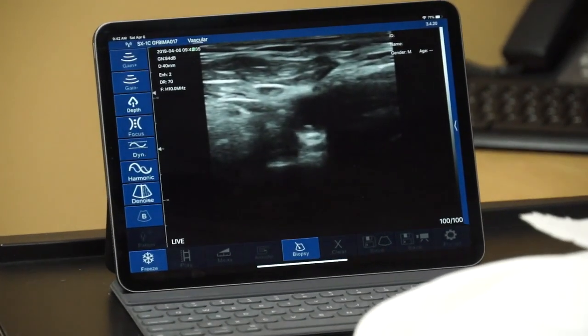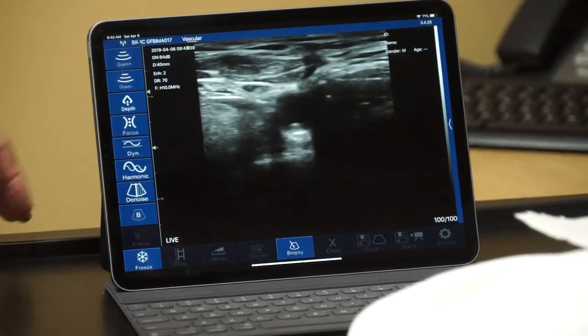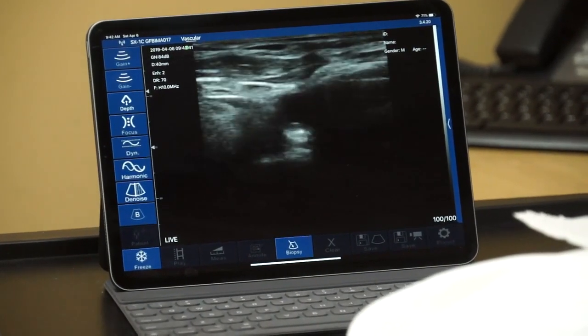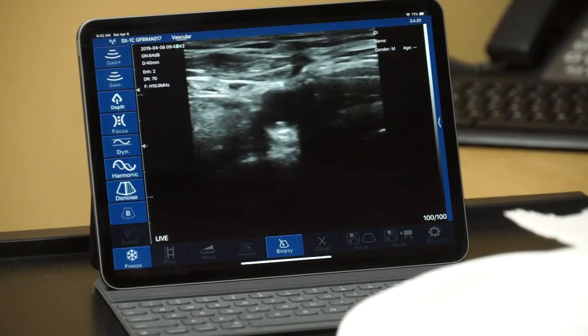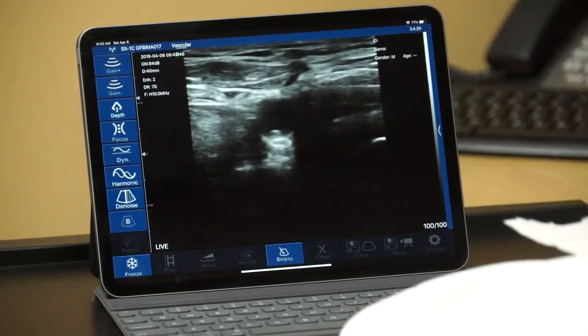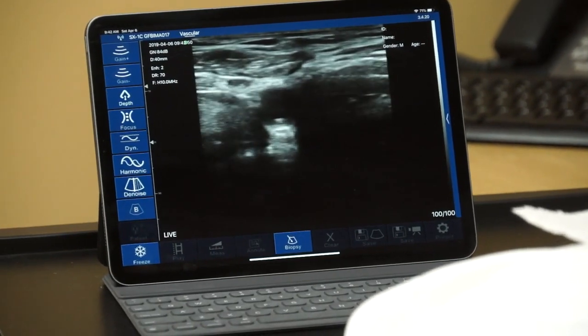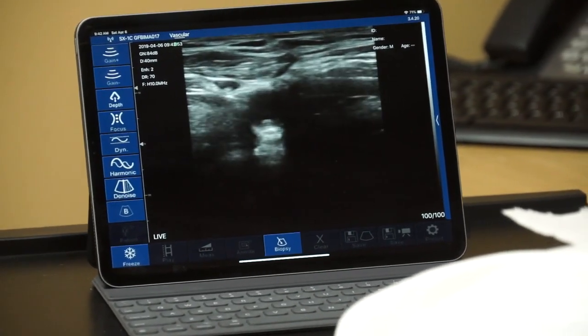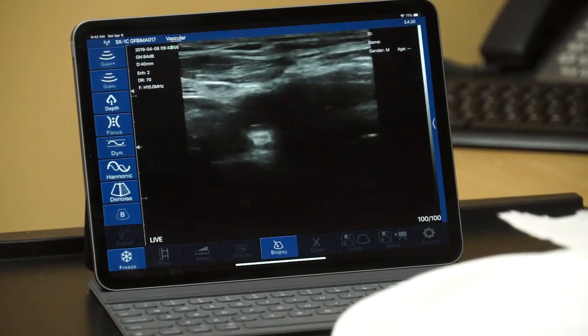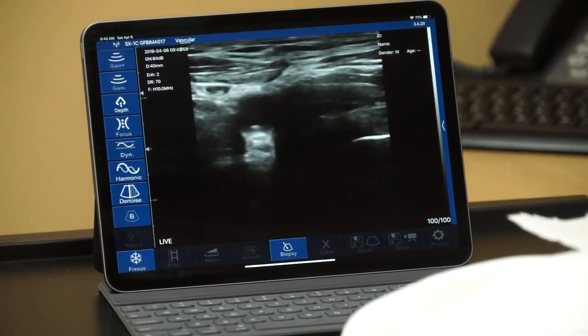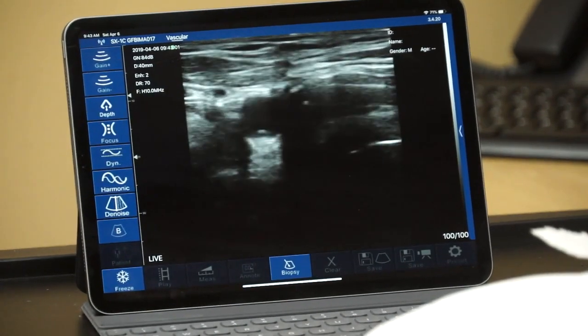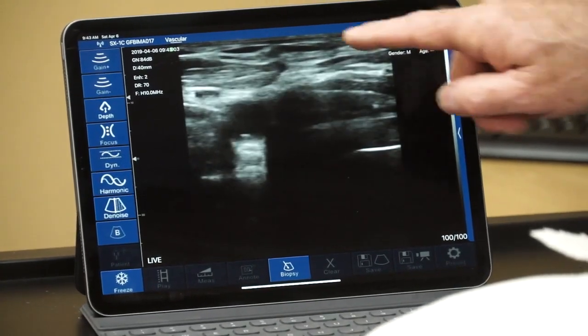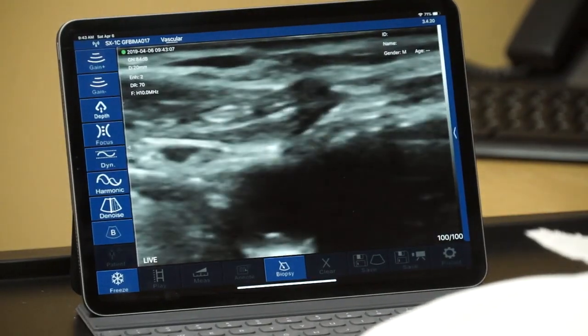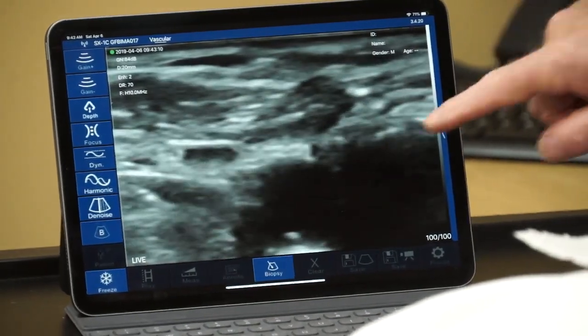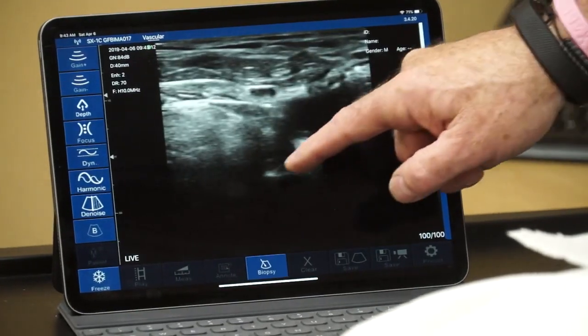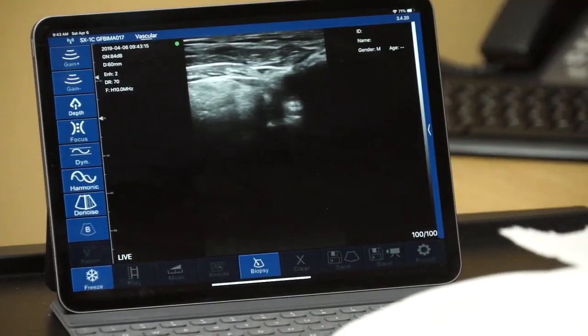Now, the next control down on the app is what is referred to as depth. Scanning depth is adjusted from very superficial to deeper. The linear probe on this device will scan from 20 millimeters up to 80 millimeters, or in other words, 2 centimeters to 8 centimeters. At this time, you can see on the screen the value listed next to the letter D is 40 millimeters. So there are two ways to adjust the depth. One is to actually move your finger on the screen, and we just went from 40 to 20 millimeters, and as we scroll the other way, we can go all the way to 80 millimeters in depth.